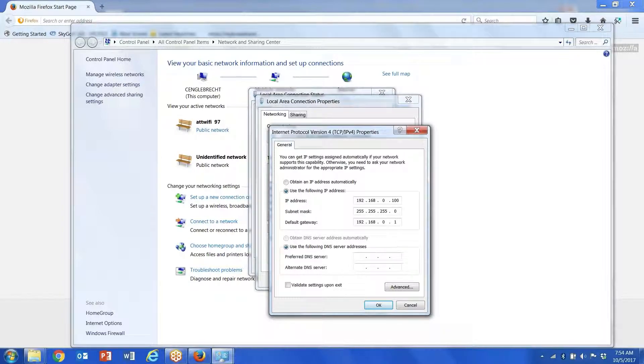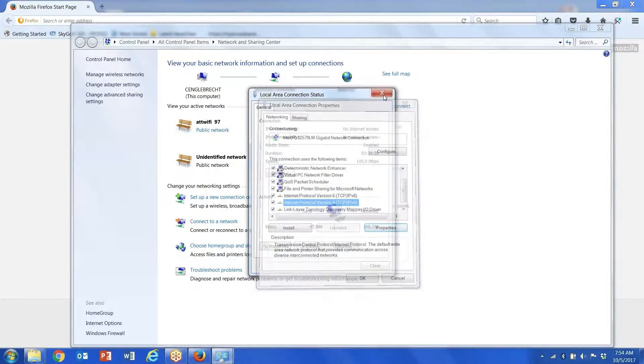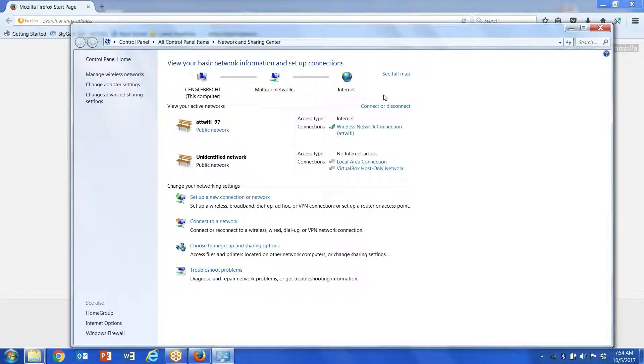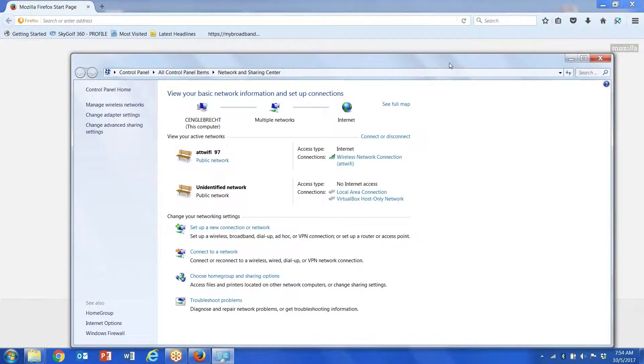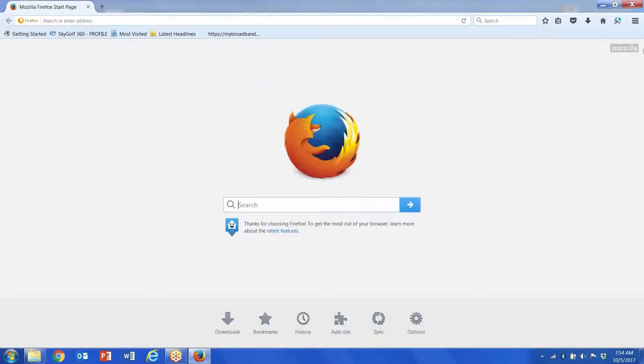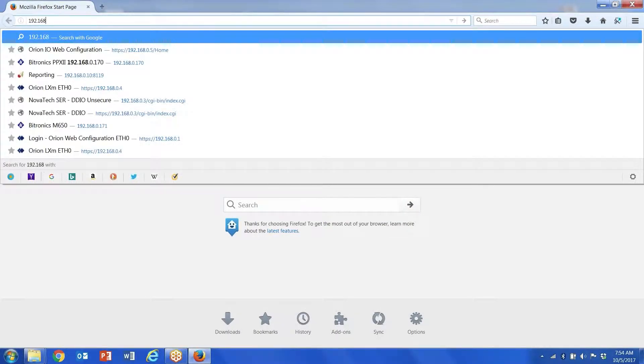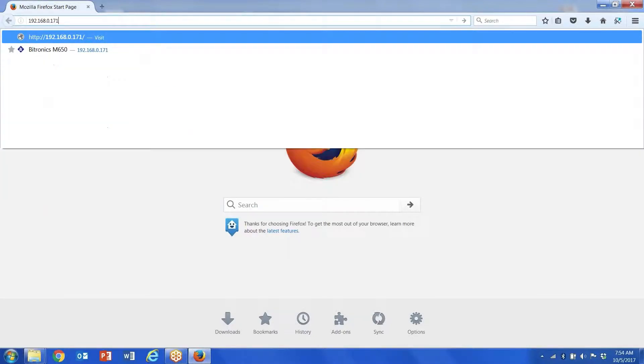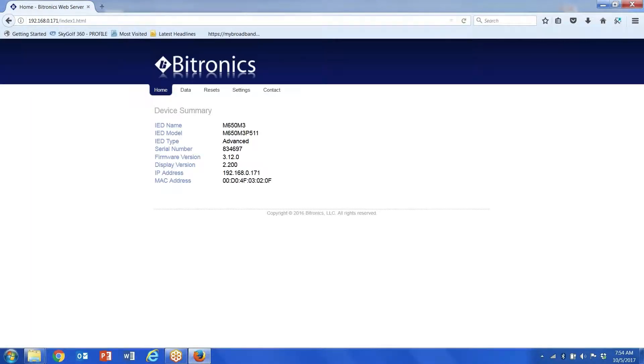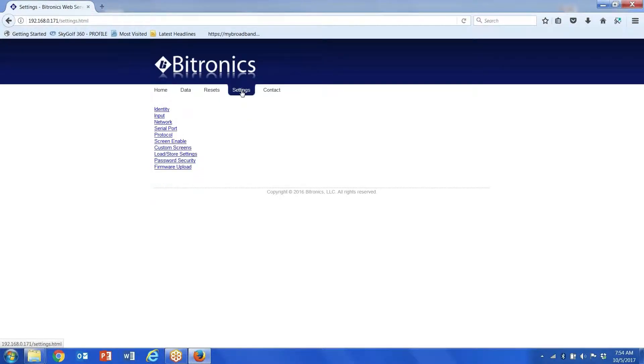Verify that under Local Area Network Connection Properties, TCP/IP Version 4 Properties, my laptop is set for 192.168.0.100. The IP address of the meter itself from the factory is 192.168.0.171, and this is what you should see when you connect.